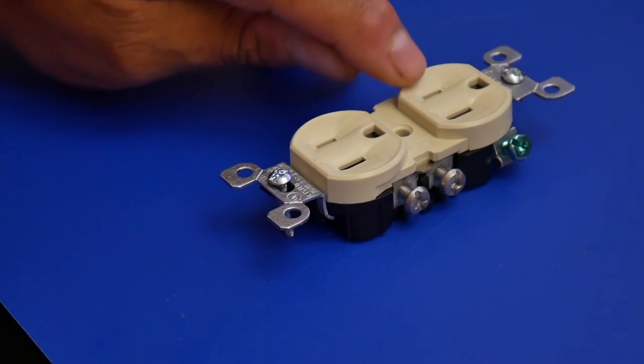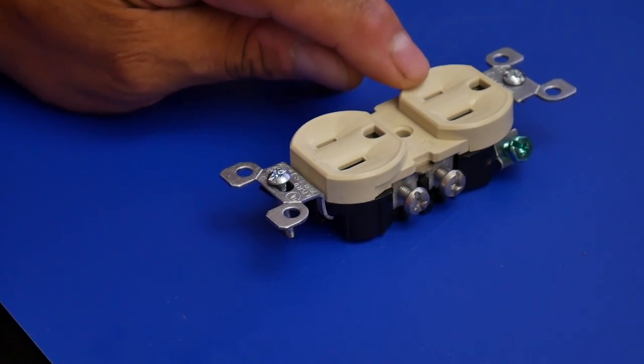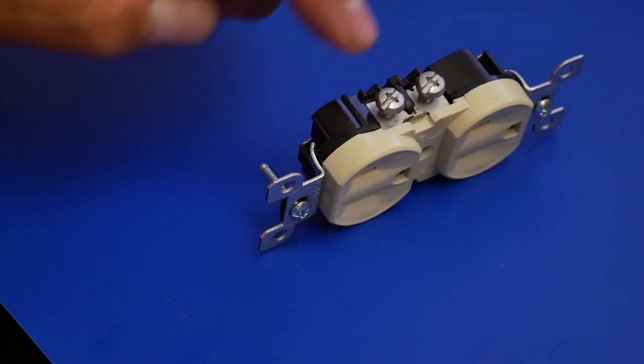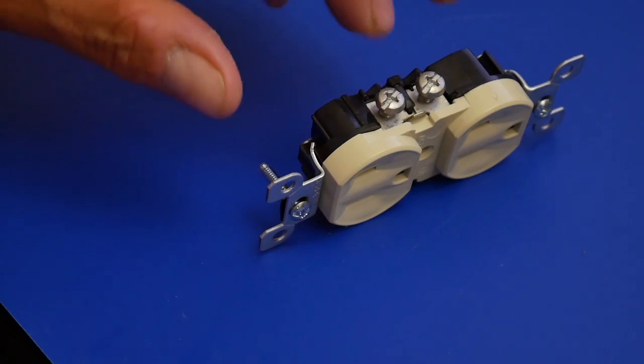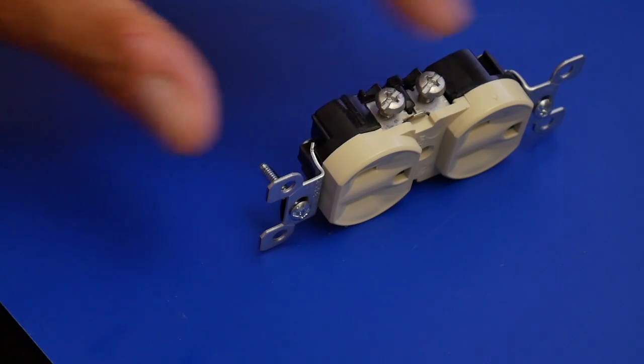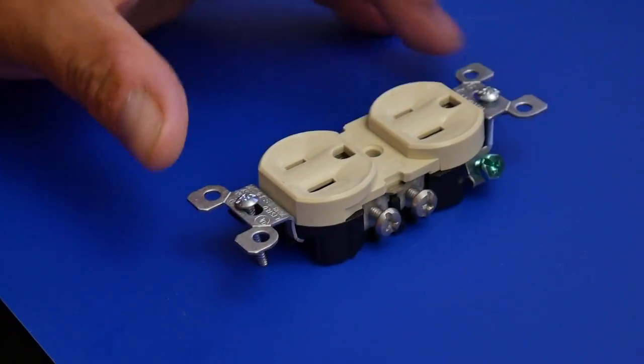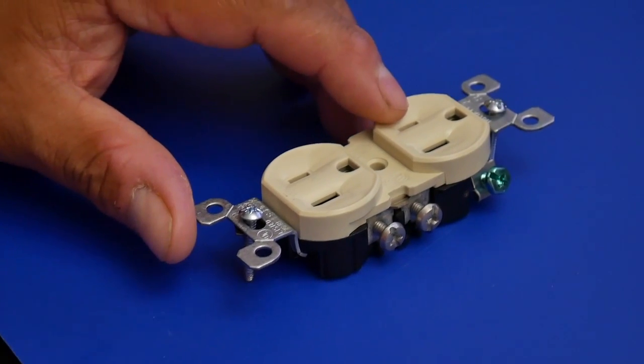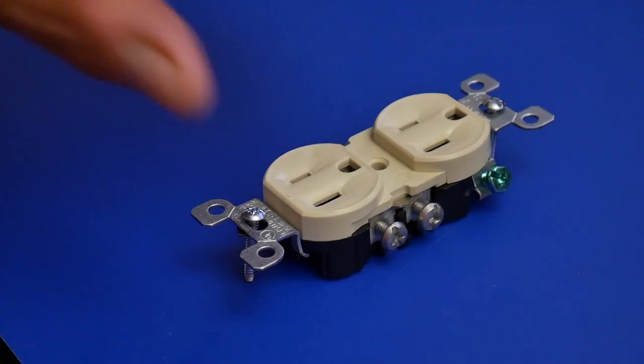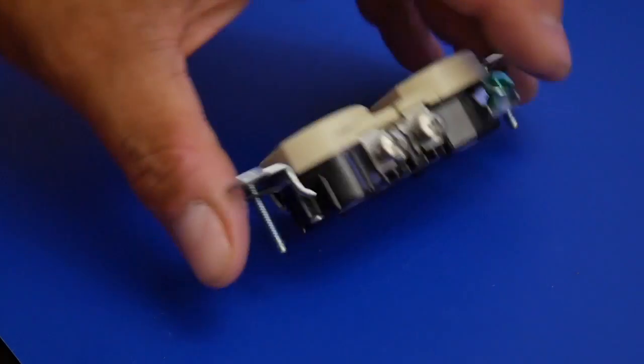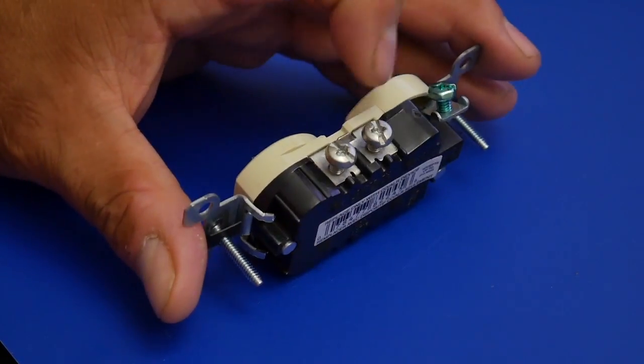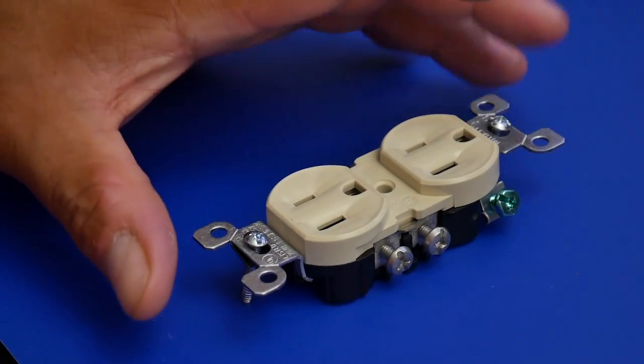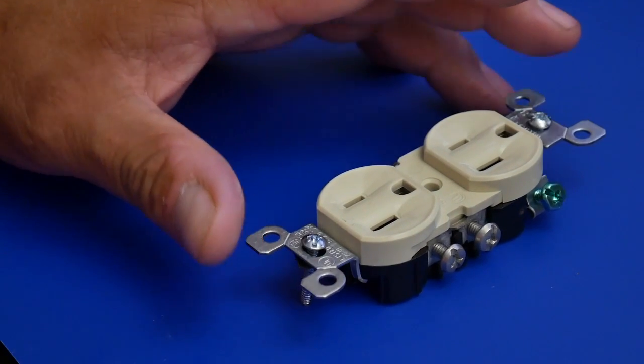The small one here is actually the hot side. You will usually see it yellow on this side. The only reason this is not yellow is because this particular device is made for aluminum wiring. The small side should be wired the hot side, usually the black wire. The larger size should be wired the neutral side, and that's usually white, the white wire. But at times you will see different things, so having a multimeter and knowing how to test would be really nice.